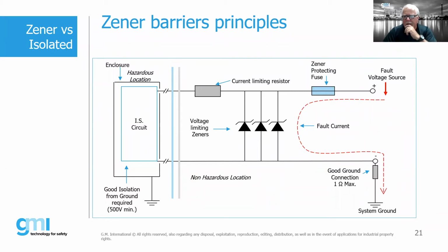Here's the important thing to know about your system ground. You have to have 1 ohm resistance maximum on your intrinsically safe earth. Also, mind you, this is a separate system ground from our normal ground. This is one of the biggest faults, and we did a webinar here on some of the common faults in the use of IS. Not having a good, clean earth is usually one of the biggest problems that I find when I do inspections. If we don't have a good clean earth, then there is nothing to shunt it to, and we have all different kinds of problems. But this is the concept of a Zener barrier.